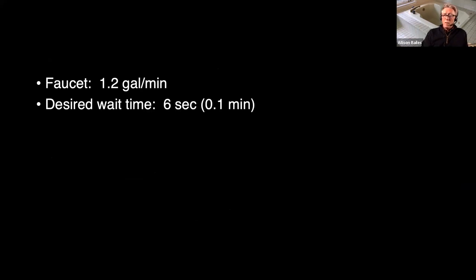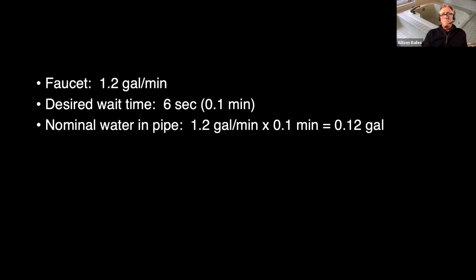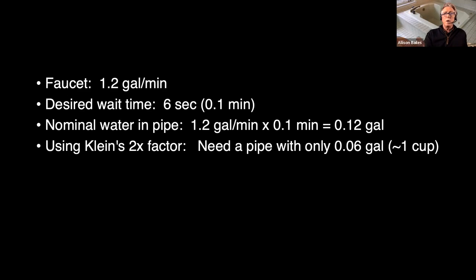If I wanted to cut that wait time down to 6 seconds, a tenth of a minute, the amount of water I'd need to push out is 0.12 gallons, but according to Gary Klein, that would mean 0.06 would actually be in the pipe. That's the factor of two we talked about.